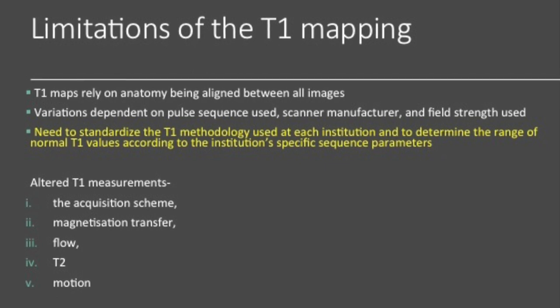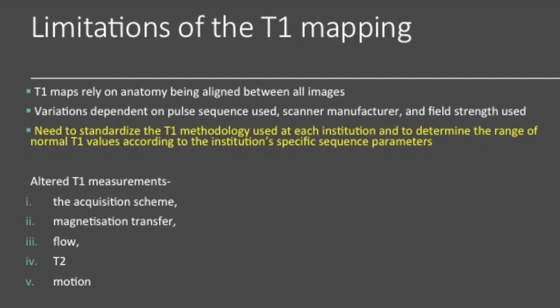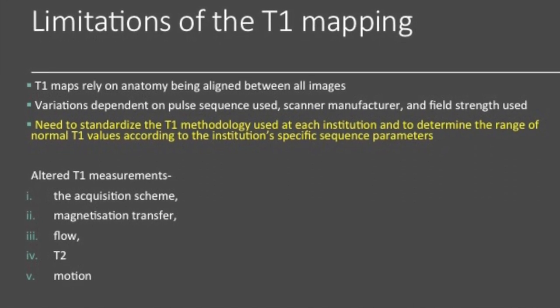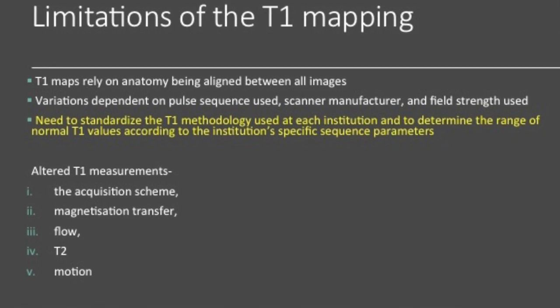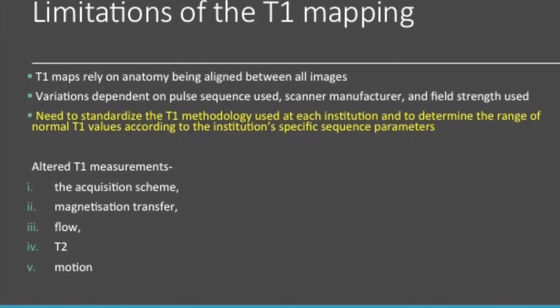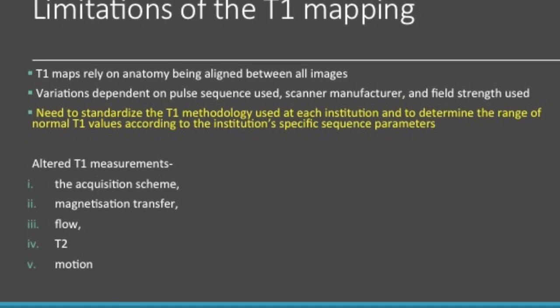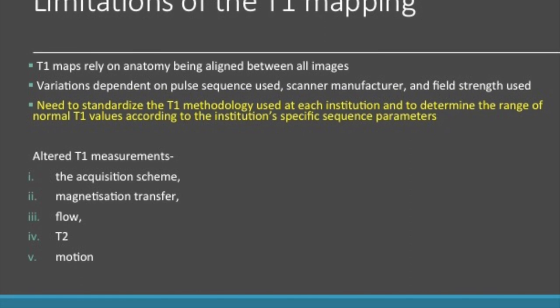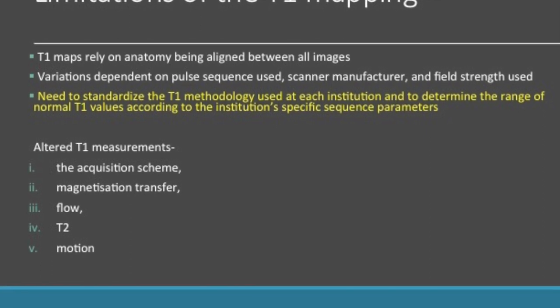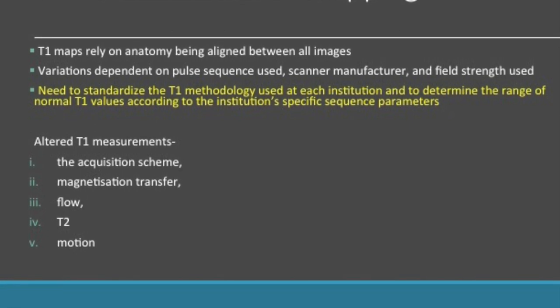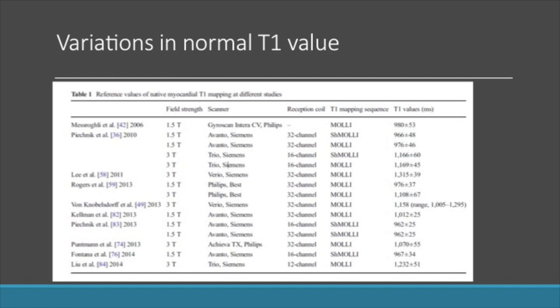Regarding limitations of T1 mapping: first, T1 maps rely on anatomy being aligned between all the images, hence the need for motion correction. Second, it is important to standardize the T1 methodology at each institution and to determine the range of normal T1 values at your scanner. Finally, the normal native T1 value, whether on a 1.5 Tesla or 3 Tesla system, is in the range of 1 second or 1000 milliseconds — slightly less for 1.5T and slightly more for 3T.